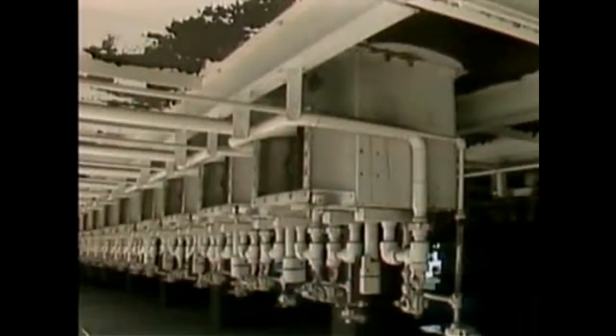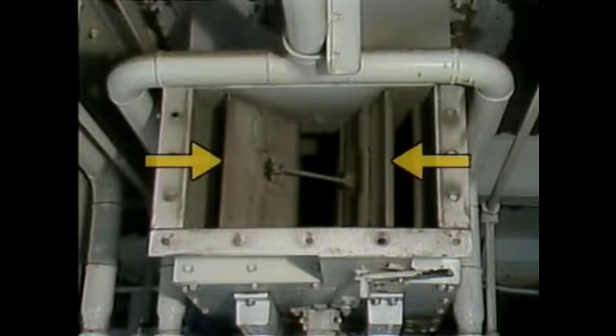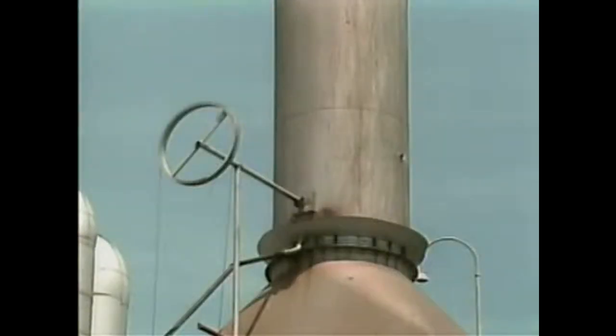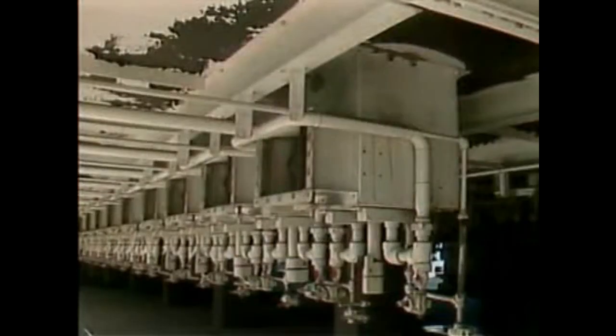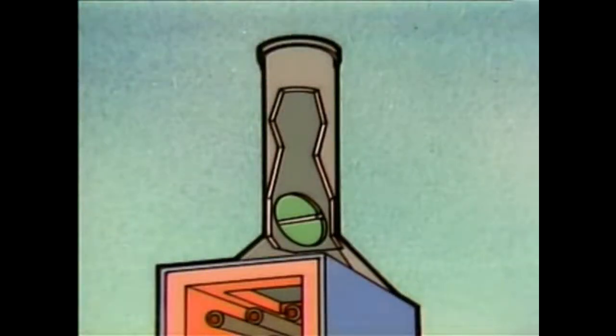An air system is needed because the burners in a furnace mix air with fuel for combustion. Airflow to a furnace can be controlled in different ways. For example, on some furnaces, airflow is controlled by registers and by the stack damper. Air is drawn into the burners through air registers. The registers can be opened or closed to let more or less air into the burner. The stack damper is used to control the flow of gases leaving the furnace. This also affects the amount of airflow that can enter the registers. Opening or closing the damper increases or decreases the amount of air that flows into the furnace.